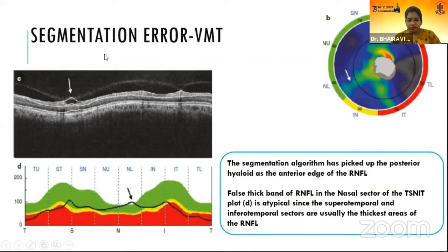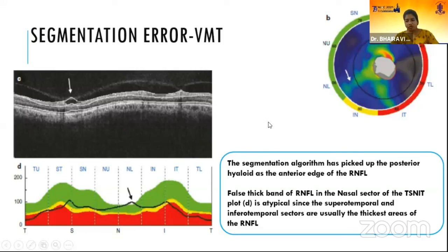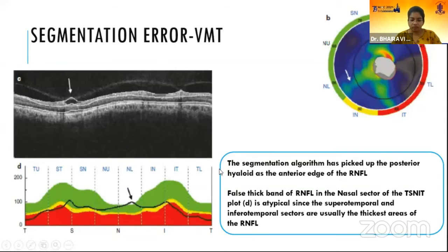Here we can see a segmentation error in the case of vitreomacular traction, where the segmentation algorithm has taken the posterior hyaloid as the anterior edge of the RNFL. In this scan of a glaucoma patient, due to abnormal segmentation, the RNFL profile in the nasal sector appears normal due to segmentation error.